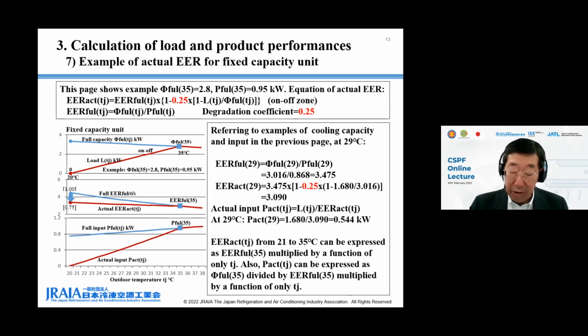Because full EER in the equation of actual EER is 35 degrees C full EER multiplied by a function of only Tj, actual EER can also be expressed as 35 degrees C full EER multiplied by a function of only Tj. Then actual input, which is load divided by actual EER, can be expressed as 35 degrees C full capacity divided by 35 degrees C full EER multiplied by a function of only Tj. ISO T1 bin hours exist from 21 to 35 degrees C. Actual ER and actual input at each Tj from 21 to 35 degrees C can be calculated in this way. Next, please.